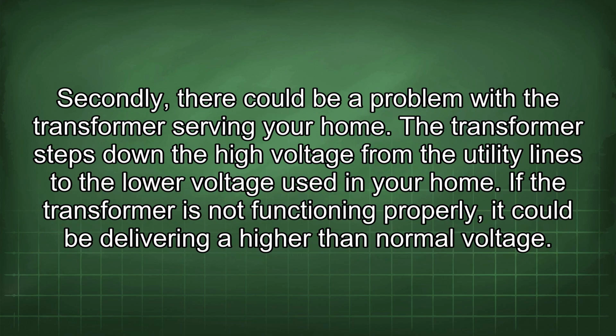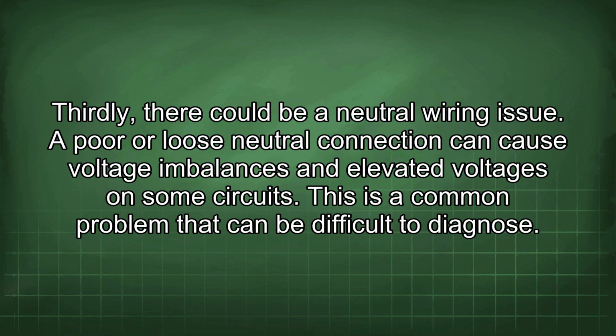Secondly, there could be a problem with the transformer serving your home. The transformer steps down the high voltage from the utility lines to the lower voltage used in your home. If the transformer is not functioning properly, it could be delivering a higher than normal voltage. Thirdly, there could be a neutral wiring issue. A poor or loose neutral connection can cause voltage imbalances and elevated voltages on some circuits. This is a common problem that can be difficult to diagnose.